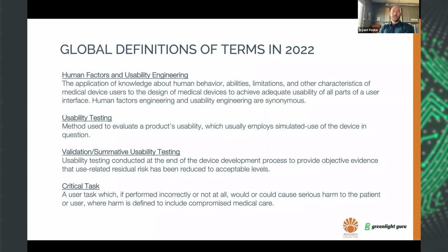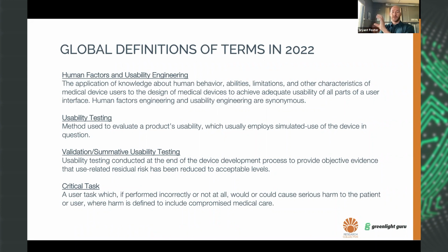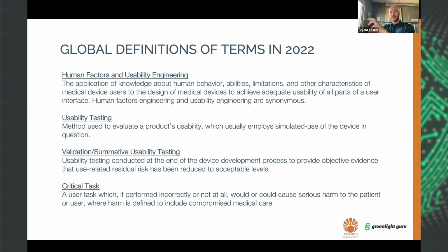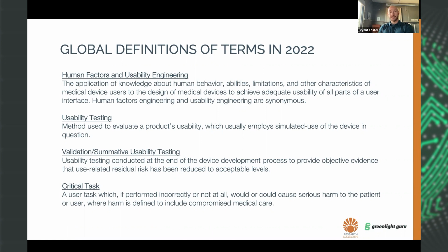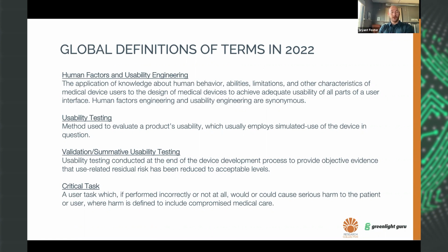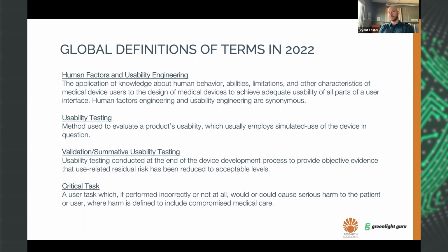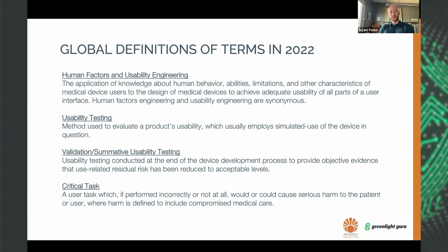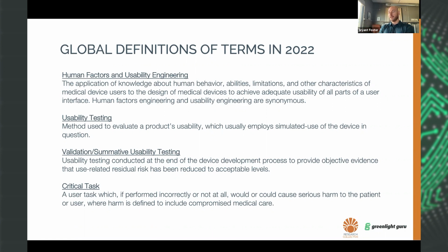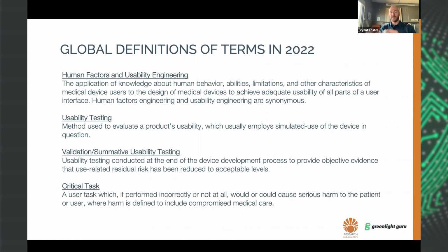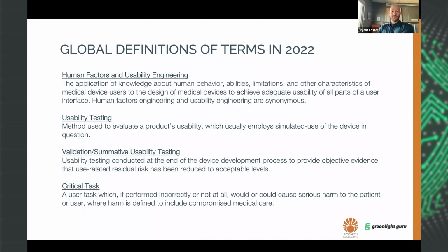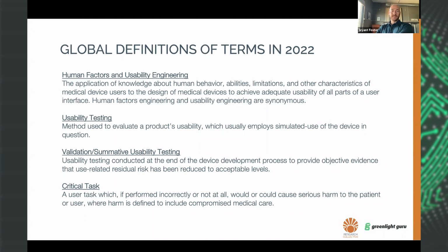It's a great question. We're going to answer that more as we go along, but essentially it's any device that has serious harm related to misuse. So if you go through the tasks that users have to perform with the product and you identify tasks that, if the user performs them incorrectly, could lead to a harm that would be considered serious, which is subjective and up for interpretation. But if you've identified that there is some use-related harm of a serious nature, then regulators will want to see that you have put this through the proper methods, doing a summative usability study to then show that that use-related harm that you've identified is not realized when it's in the hands of the users.